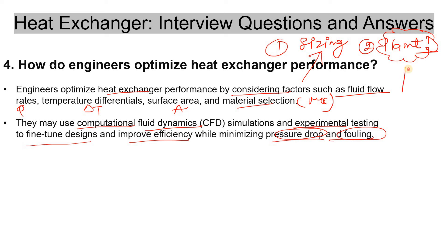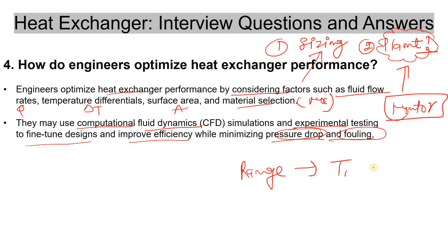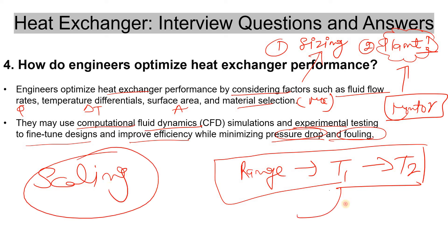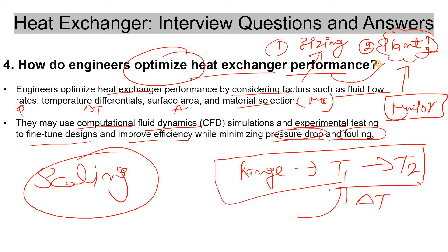When there is a heat exchanger in the plant, engineers optimize by monitoring the temperatures — checking whether the designed delta T is being achieved. If there is some scaling, you can identify it from the temperature readings. Actions include cleaning the tubes, performing hydro jetting, back washing, or chemical cleaning to optimize the heat exchanger already erected in the plant.